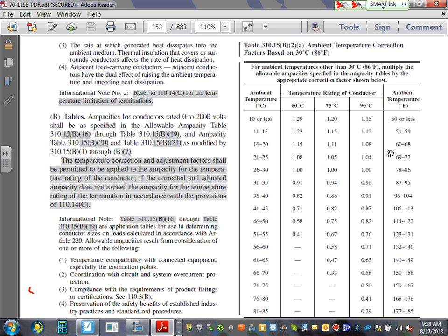This is going to be work in progress. Between these tables that I walked you through today, you're going to be sizing for all the commercial industrial projects. So later on, we're going to have a commercial project, 4,000 amp. You're going to go size for 4,000 amp. Which table are we going to use? 310.15(B)(16). Cut the 4,000 amp into 10 runs, 400 amp each, and go size your conductors. Any comments, any questions? Cool. That's what I wanted to emphasize a little bit. Again, if it's too much for you the first time, we're going to hit this one three times. By the third time, you better know how to use them really well.